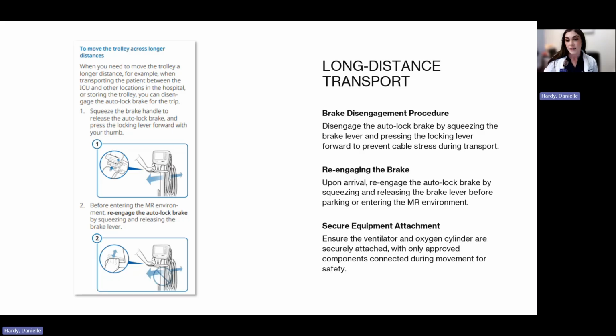Upon reaching the destination, re-engage the auto lock brake by squeezing and releasing the brake lever before entering the MRI environment or parking the trolley. Always verify that the ventilator and oxygen cylinder are securely attached before transport and that only approved components such as the breathing circuit, the HME, flow sensor, and the oxygen cylinder remain connected during the movement. Following these steps helps ensure safe and efficient transport while protecting the trolley system from damage.